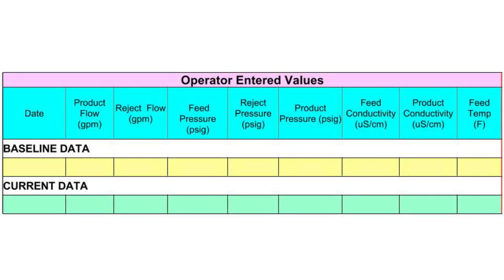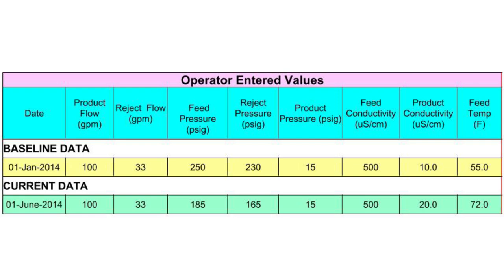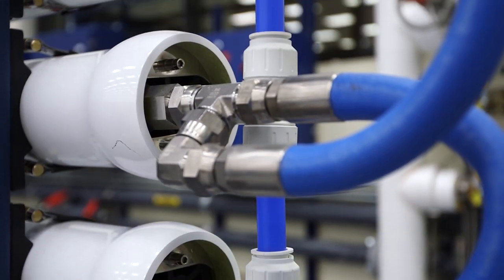Here's a typical normalization spreadsheet. Baseline data should be collected about two days after new RO membranes are installed. Here's an example of data collected January 1st and June 1st. Without taking feed water temperature into account, the lower feed water pressure and higher product conductivity in the June data indicate RO membrane damage. The normalized percent permeate flow, which takes the change in feed water temperature into account, actually shows RO membrane fouling because the normalized percent permeate flow is lower than baseline. We recommend you collect RO data at least once per week and have a service technician from an outside vendor evaluate the data at least quarterly.